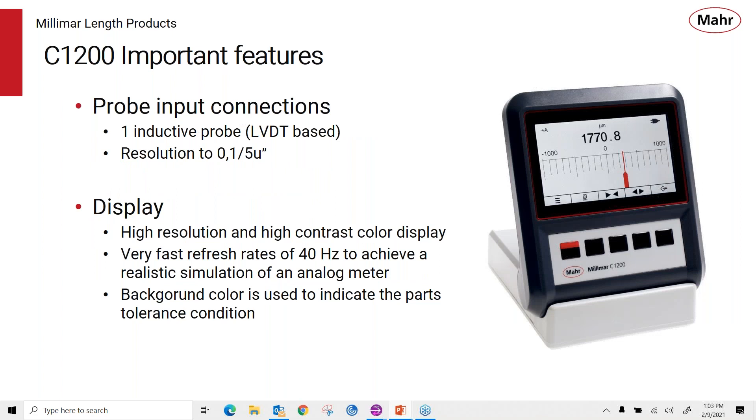The C1200 features include its one probe input — it's an LVDT-based probe input. It's a very fast, very high response, high precision LVDT. We build the accuracy into Mahr's probes where you can get 0.1 micron or 5 micro-inch resolution, so it's a very good amplifier that gives you high quality performance. The display is a high resolution, high contrast color display with a very fast refresh rate of about 40 Hz or better.